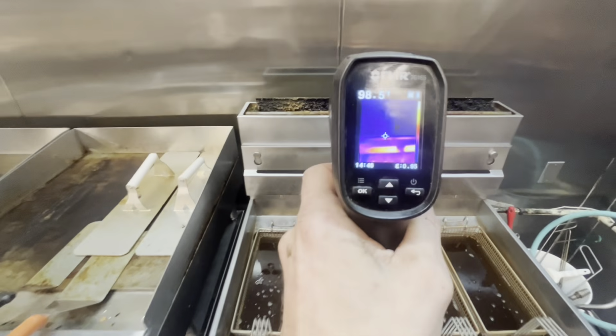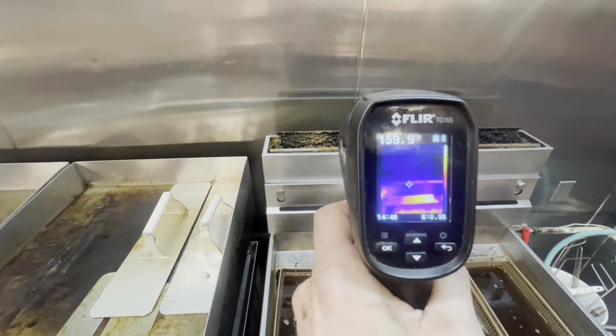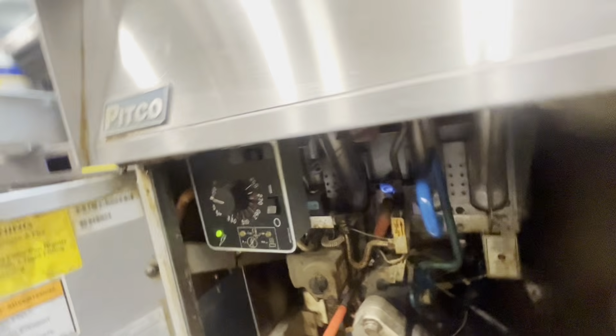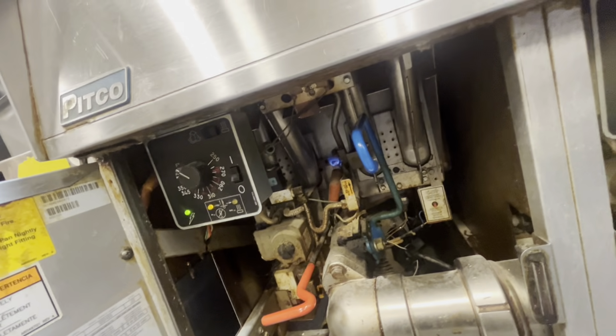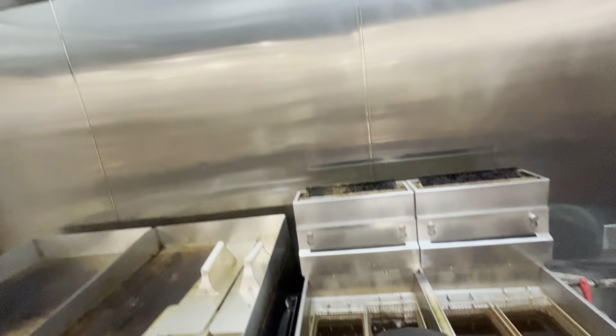Your left burners are lit, but they're not getting the proper combustion. The screens on the filters are going to be clogged. So these tubes have to come off, but it's a pain with these fryers because you have to actually take off this whole self-cleaning, burning thing. I hate that; it caused the fire at the other store. But you have to take that out, drop the valve, remove all 4 of the burners, and then even though this looks clean, I guarantee you, you've got some obstruction problems on the left 2 burners based on, let's fire back up, just look at the heat signature output.